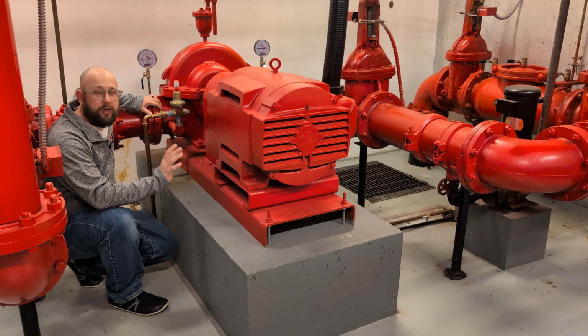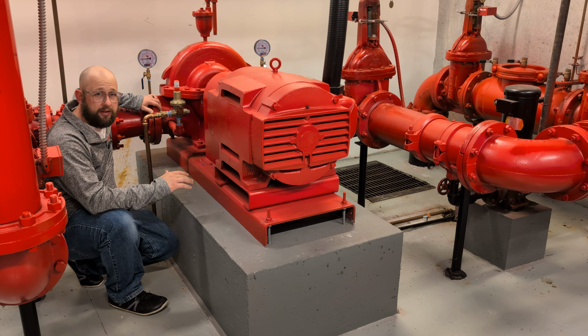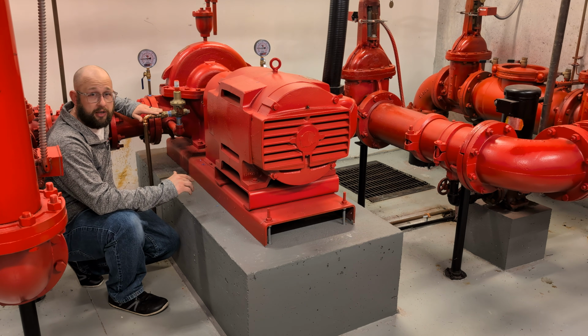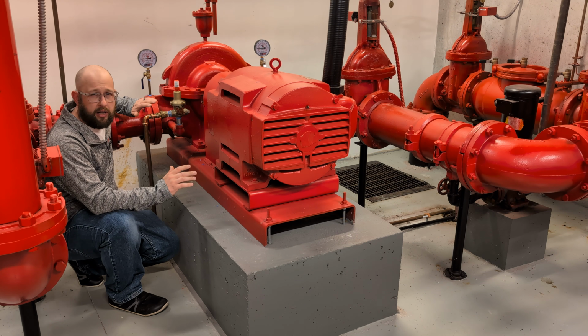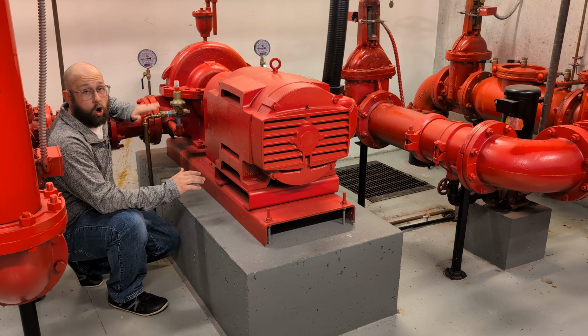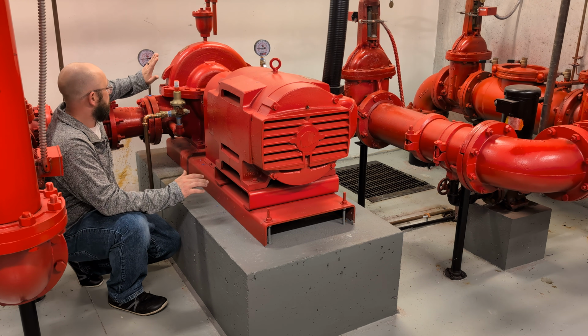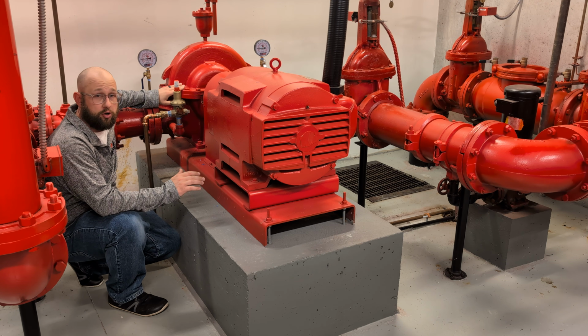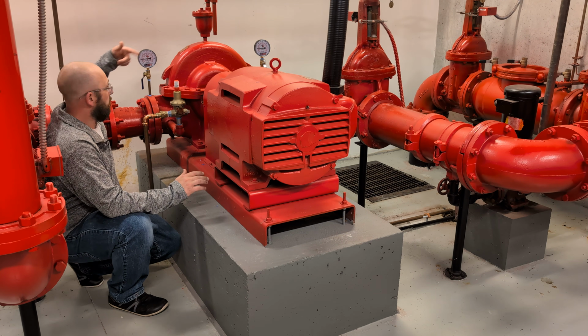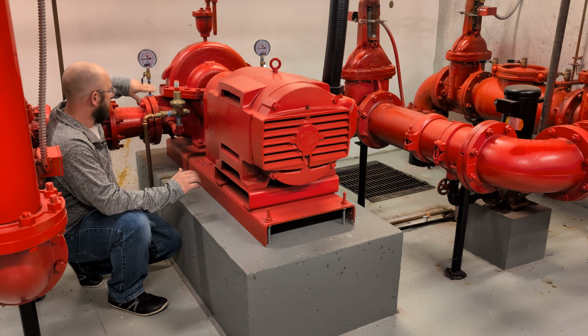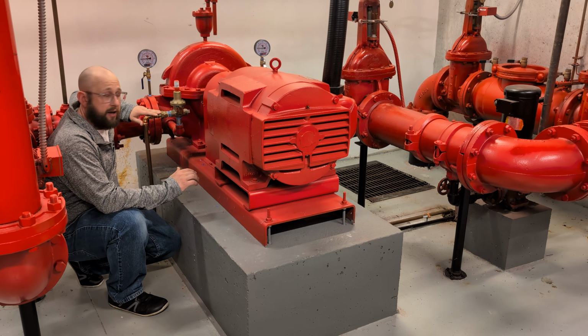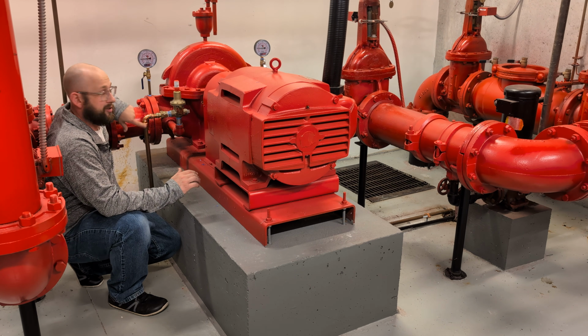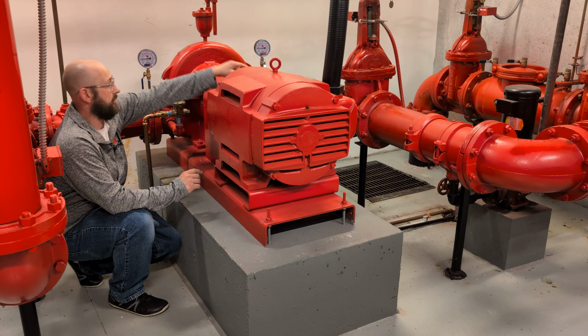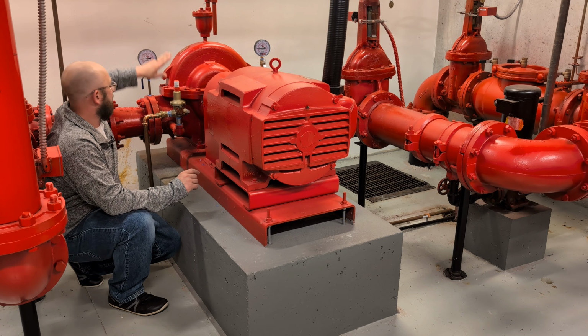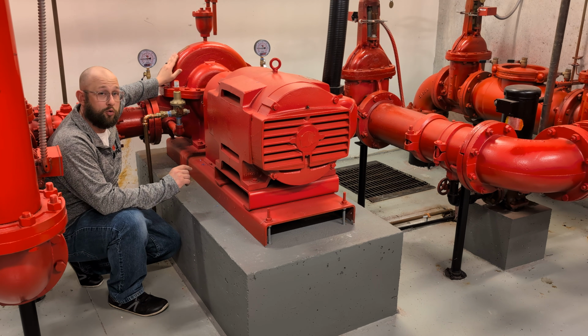So the next question we got was around circulation relief valves. This is an example of a circulation relief valve. I think the question was whether or not they were required. Basically, they are required. So what a circulation relief valve does is it is meant for when the pump itself is in the churn condition, meaning it's pumping water, but it's not going anywhere. We're not flowing anything. This circulation relief valve is meant to open up to allow some water to flow out. You can see over there it goes out to the drain. That allows for this pump itself to be cooled.